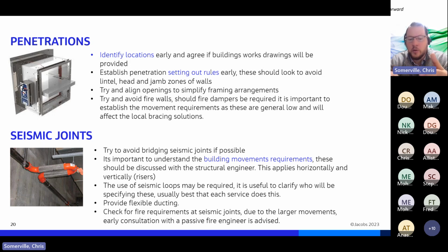You want to avoid putting penetrations through lintels, head and jamb zones of walls and any openings, and try to line up openings so cable trays aren't staggered through a wall, because that really complicates how you frame out and restrain the wall. If you can create a more unified, logical approach, that's always good.